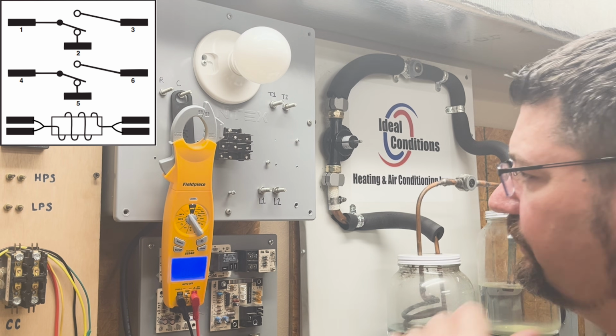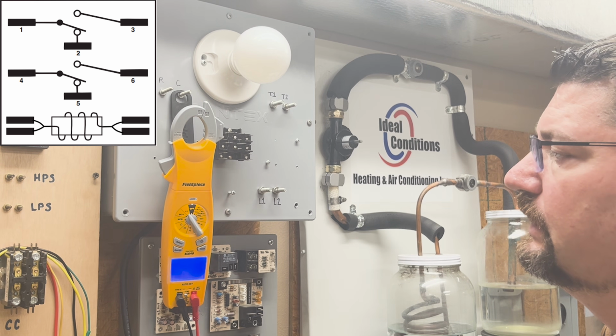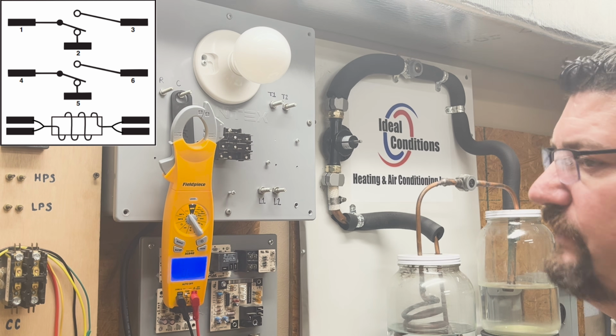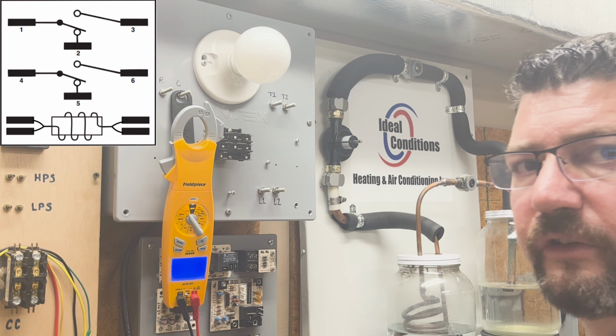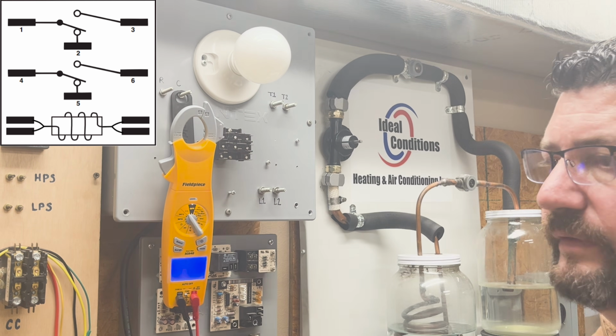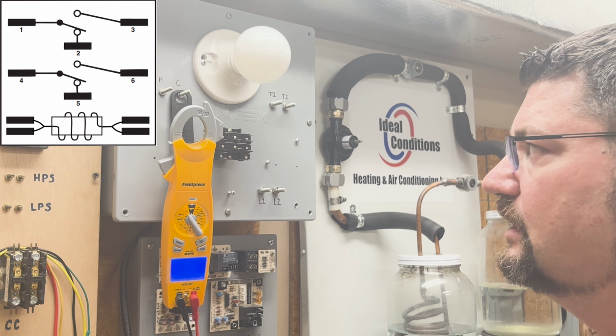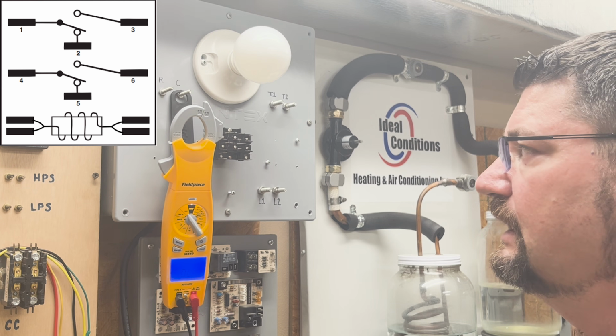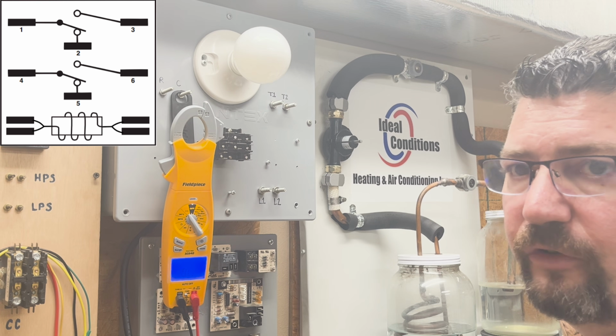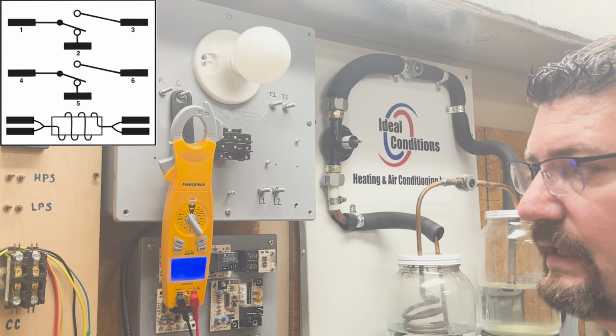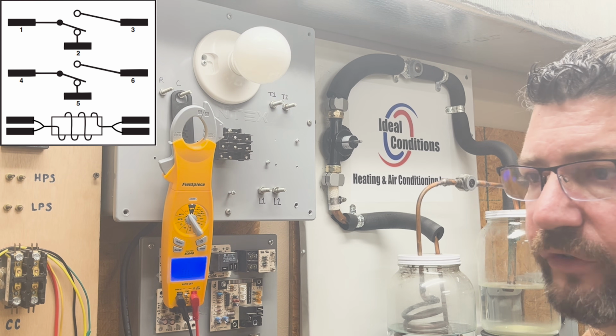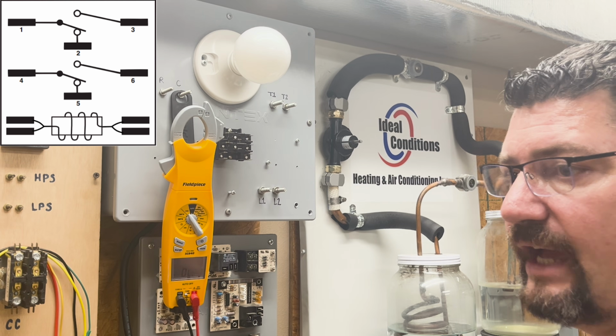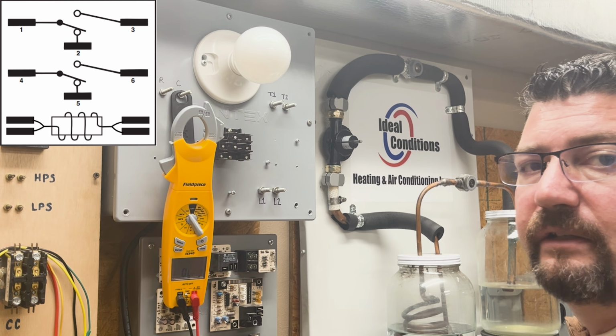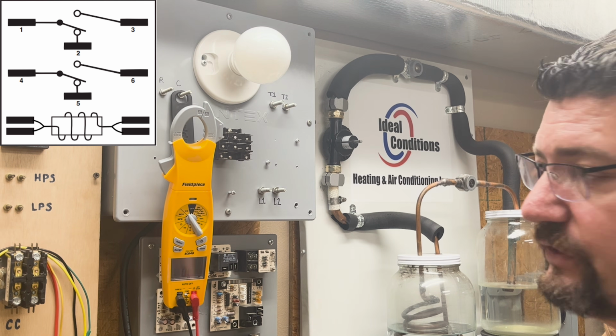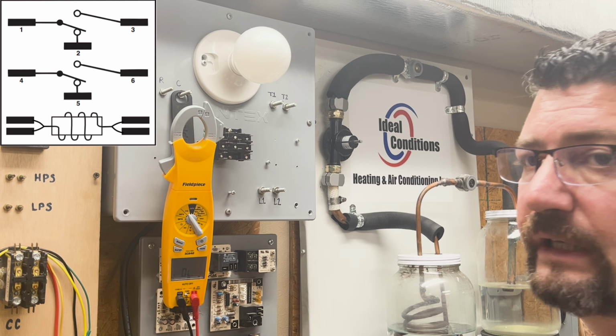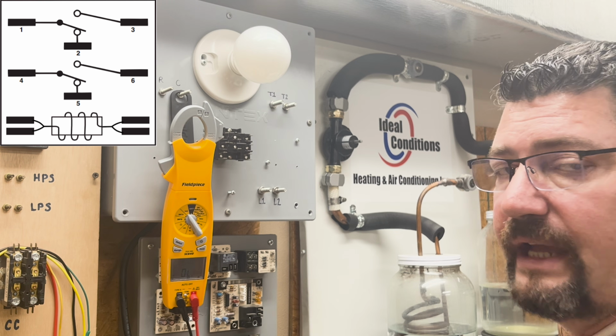Now some meters, they don't have a ringtone. Some of them do. It doesn't matter. If you're reading, you're looking for the numbers. So if you're not seeing numbers there, then it's contact side. If you're seeing numbers there, then it's coil side. Make sure you're on the right voltage so your coil doesn't say 24 volts and your coil voltage that you have on your unit is 208, because that would not be good. That's going to create a lot of work, create a lot of problems, and somebody's probably going to have to come over there to help you out if you made that mistake.